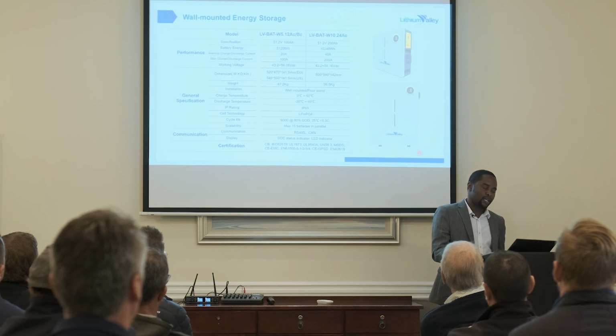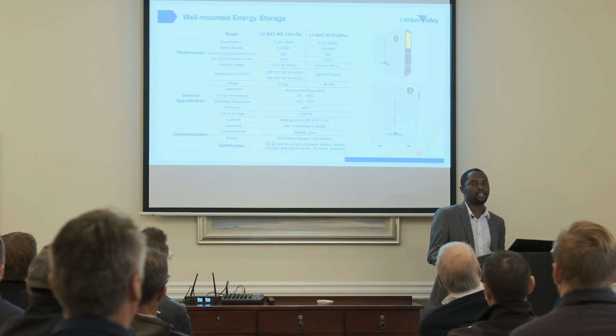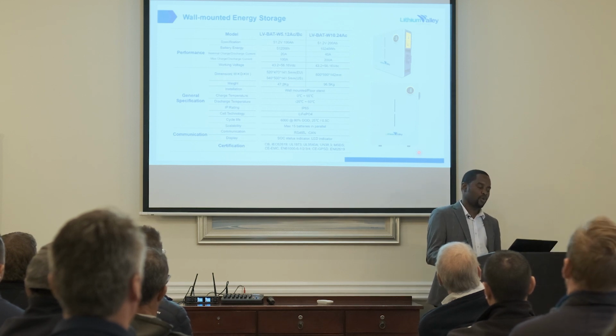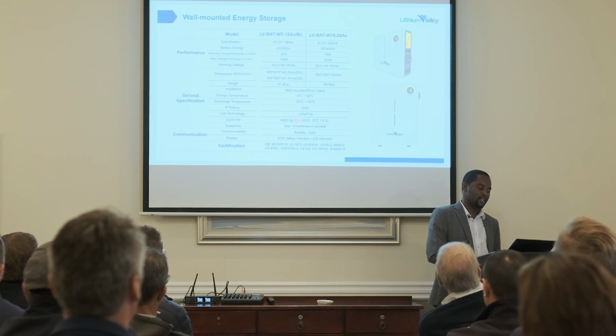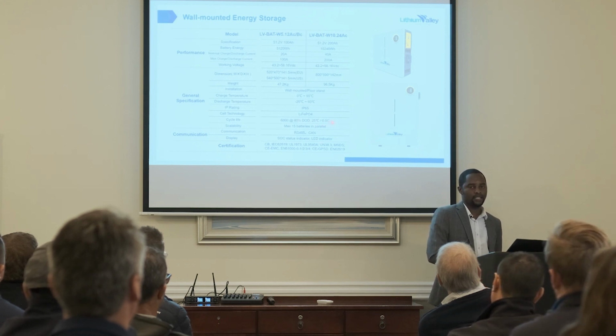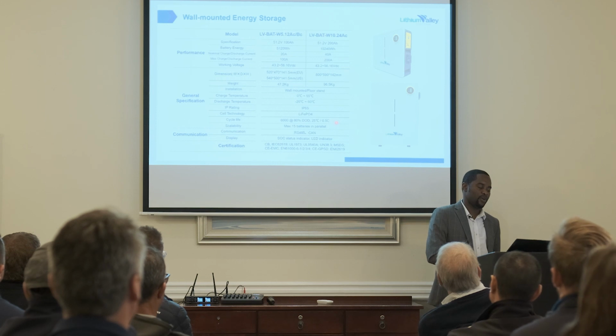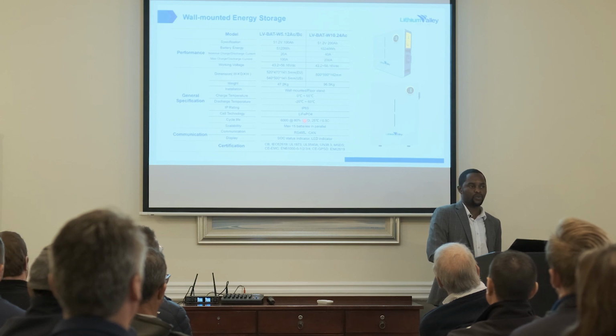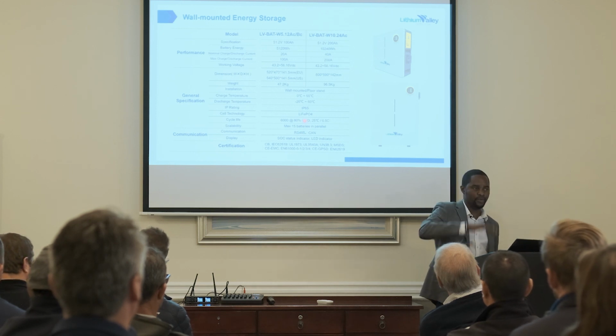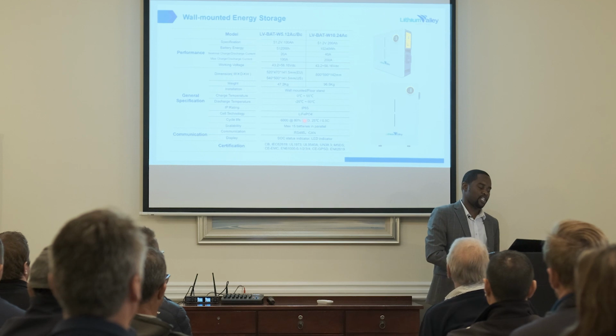6,000 cycles at 80% DOD, the end of life 80% again, then 25 degrees when you are running at 0.5 C. So what this line is saying, they are confirming that when they did the tests, simulating those tests, they were not at 1 C, they were at 0.5 C, and the temperature was controlled at 25 degrees. They were not draining it until it's 0, they were draining it until it's 20%. So 80% DOD, you are using only 80% from 100. At 20%, you are shutting it off, right?